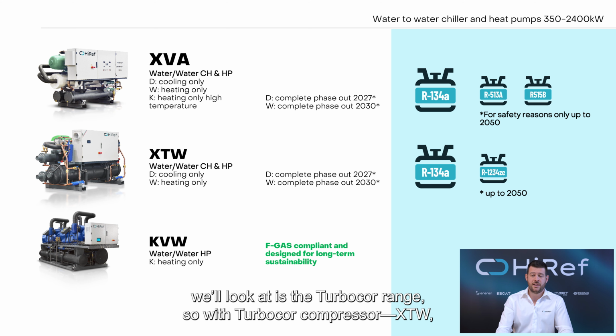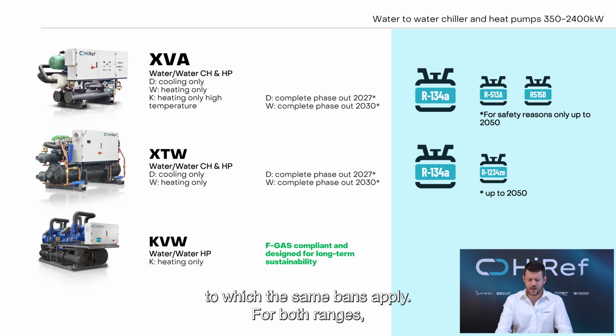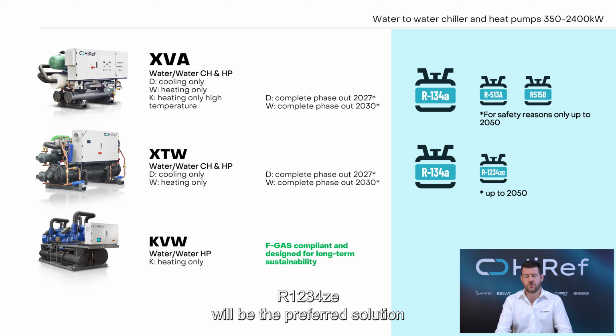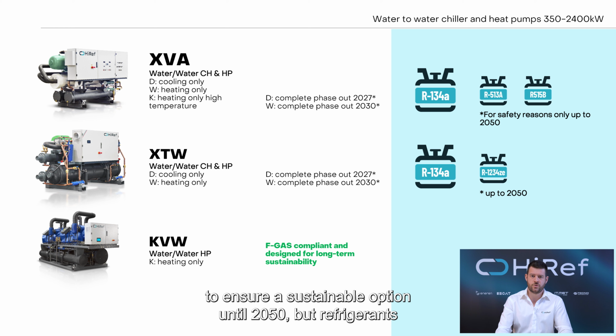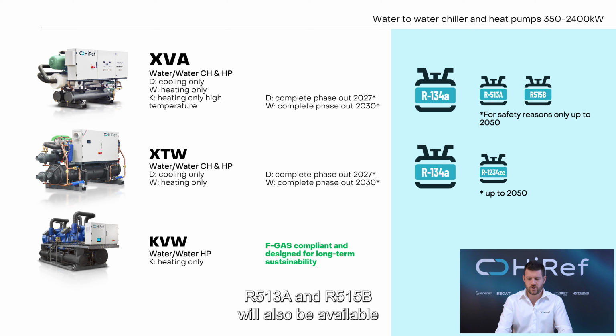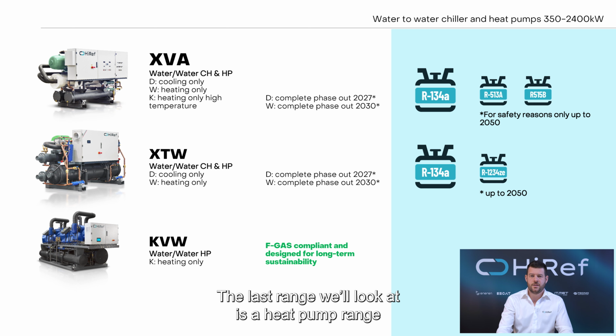The second range we'll look at is the Turbocor range, so with Turbocor compressor, XTW, to which the same ban applies. For both ranges, R1234ze will be the preferred solution, to ensure a sustainable option until 2050. But refrigerants like 513A and 515B will also be available, only for safety reasons, until 2050. The last range we'll look at is a heat pump range for high temperature water production, available with 1234ZE refrigerant. So from an F-gas perspective, it's compliant until 2050 and still a sustainable and long-term solution.